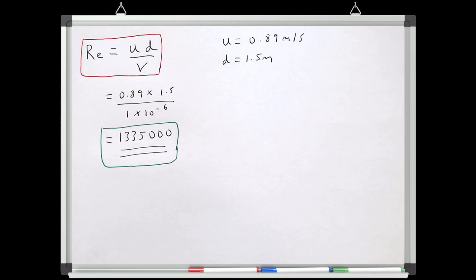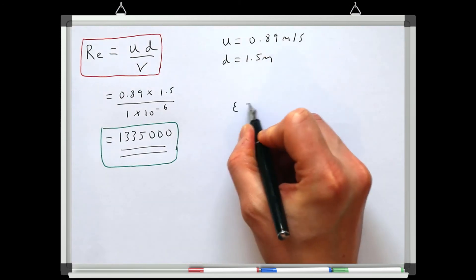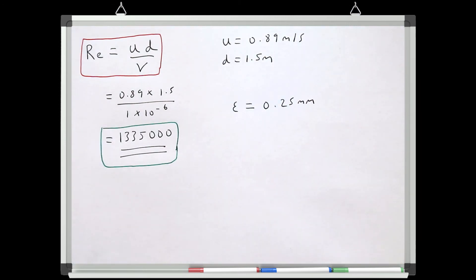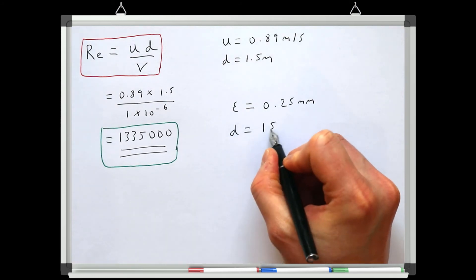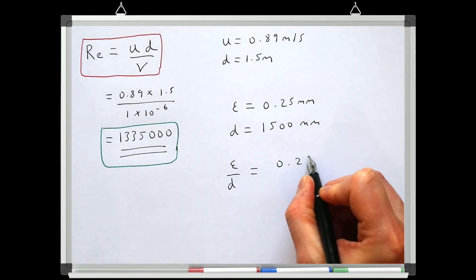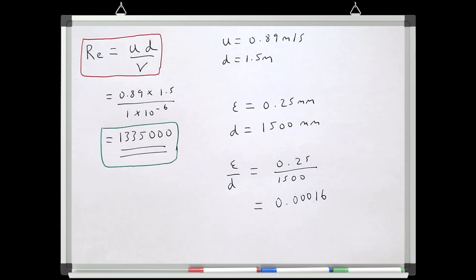But I've made an estimate of the roughness of the pipe in this system as 0.25 millimeters, which seems like a reasonable estimate for the type of materials used in systems like this. And if we divide that by the pipe's diameter, we get the relative roughness as 0.00016.